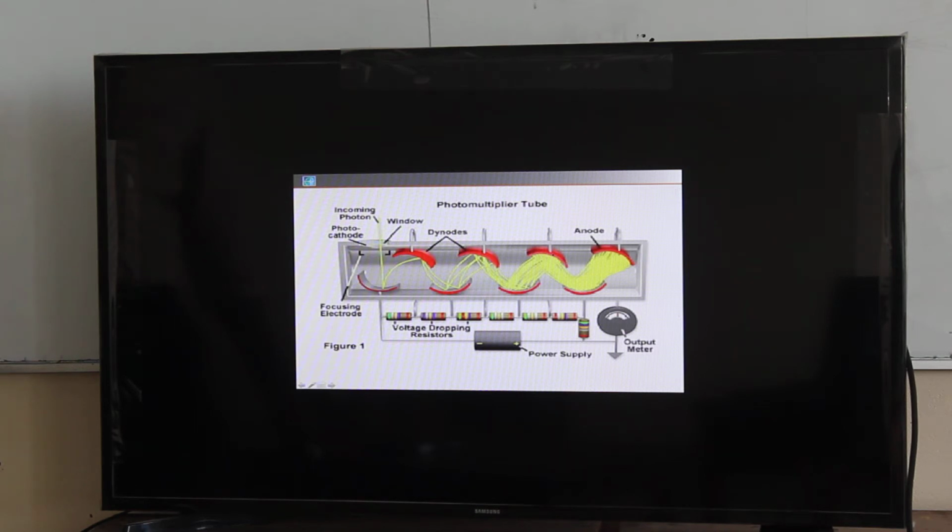There are all kinds of shapes and sizes for photomultiplier tubes. Most of them look like about the size of a soda can. So it looks like this. The photon would come in at the front end here, and you notice that window has a coating on the inside, so it looks a little dark. That's the material that has a low work function and ejects an electron. And now that electron is accelerated down the dynode chain throughout the volume of this tube.